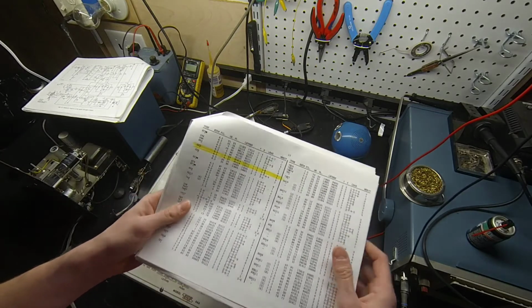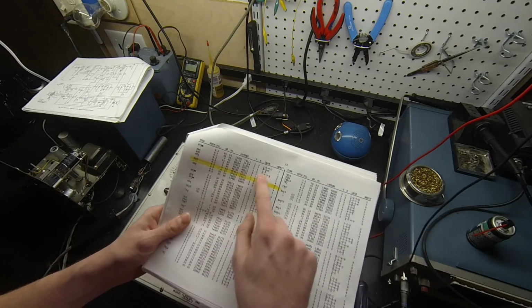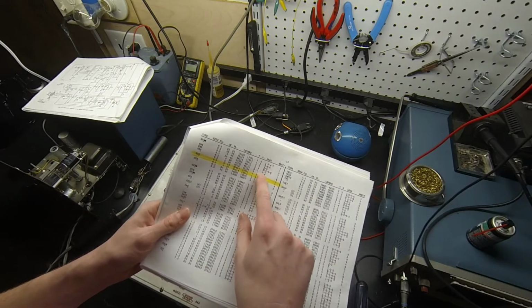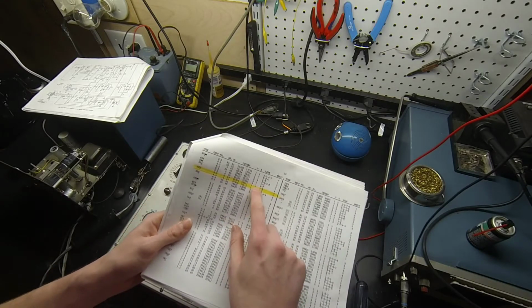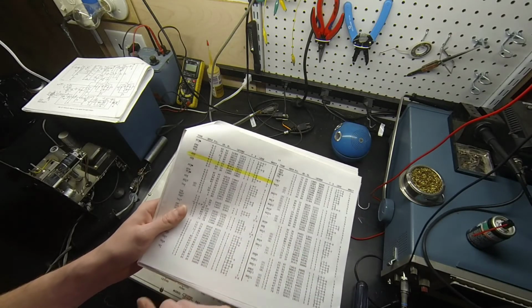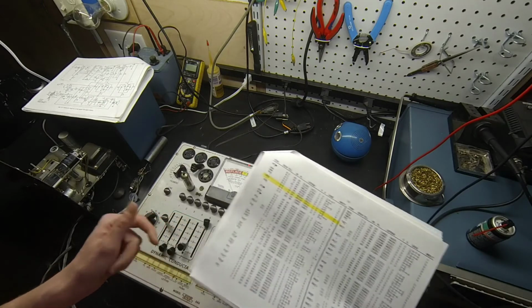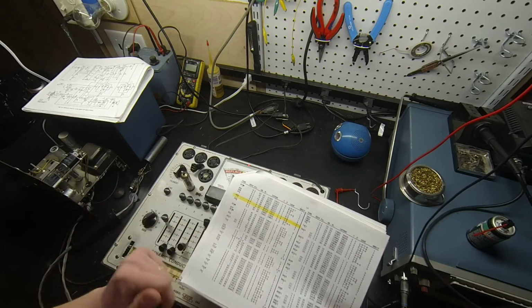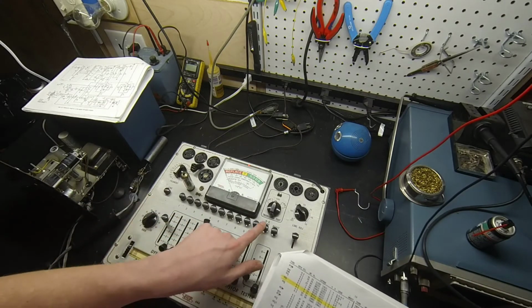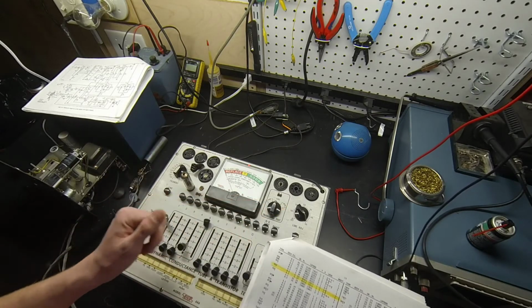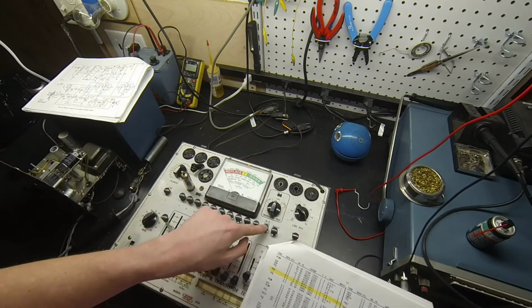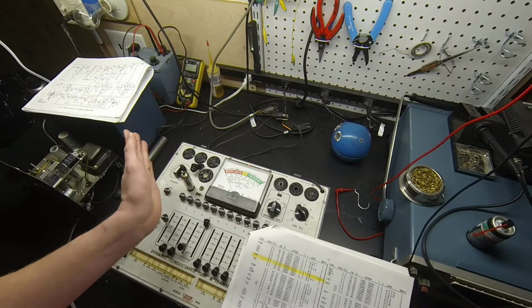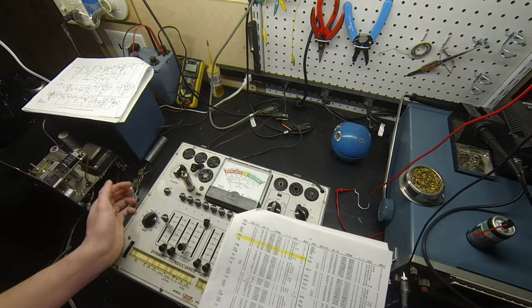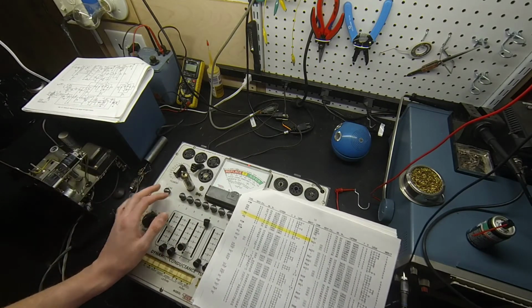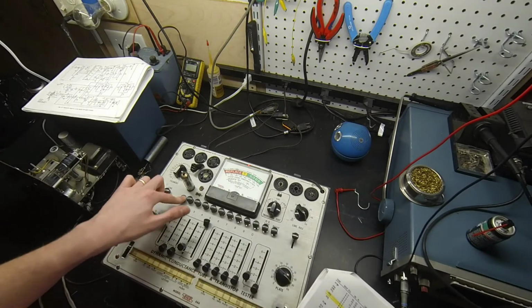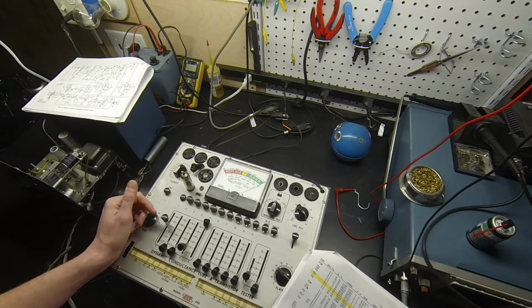Now it may be hard to see, but if you look at the buttons it's talking about, 1 and 7 here for the first side of this tube. The 7 has an underline. Any number that's underlined, you hit the heater cathode leak button, because it will automatically pin that, and you hold this button to make sure it goes back to 0, indicating there's no short. So we're checking 1 and 7, and right out of the gate, when we hit 1 here, it immediately pushes that needle over.